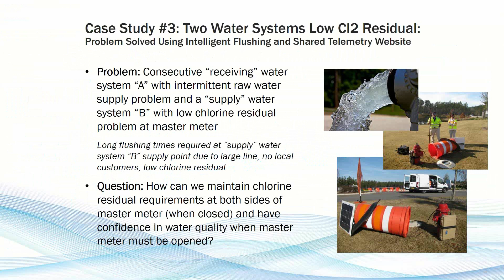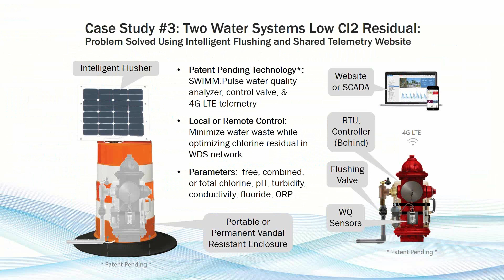I just want to show you briefly the technology that was utilized. So this was a temporary install. It's been installed for maybe a year, but we put out our SWIMM.Pulse water quality analyzer and intelligent flusher, and we can monitor various parameters based on the project, whether it's free or total chlorine. For this project, we were monitoring turbidity as well in the upstream, free chlorine, pH and temperature. And the beauty of this kind of system is it takes about 30 minutes to install, and then data is hitting the website, and you're controlling the amount of flushing that's occurring for your analyzers and for your piping network, and you're keeping water quality at your desired target regulatory requirement.